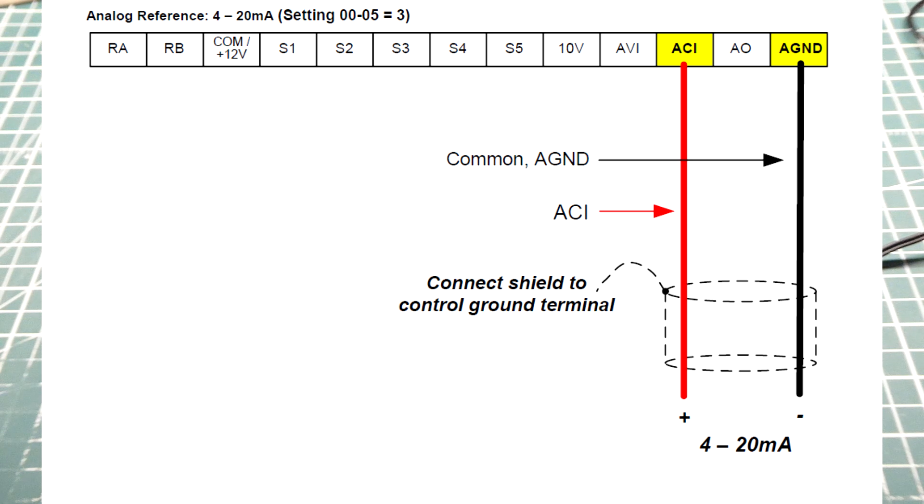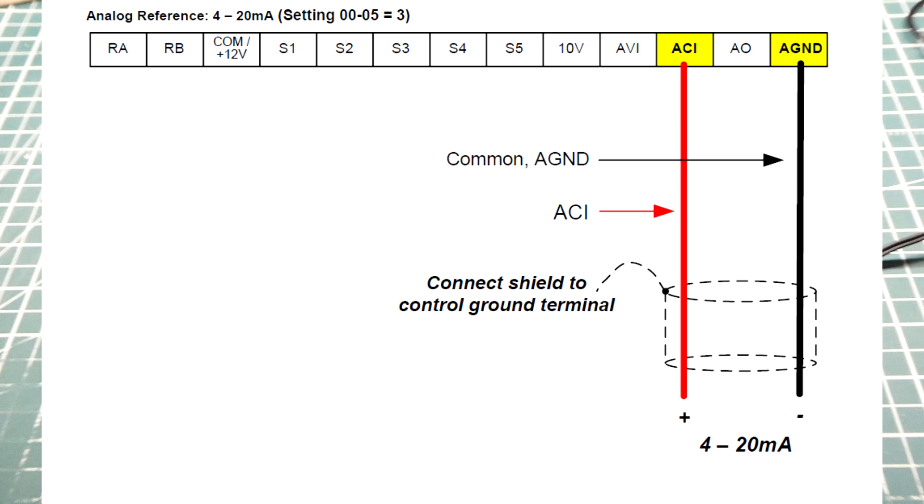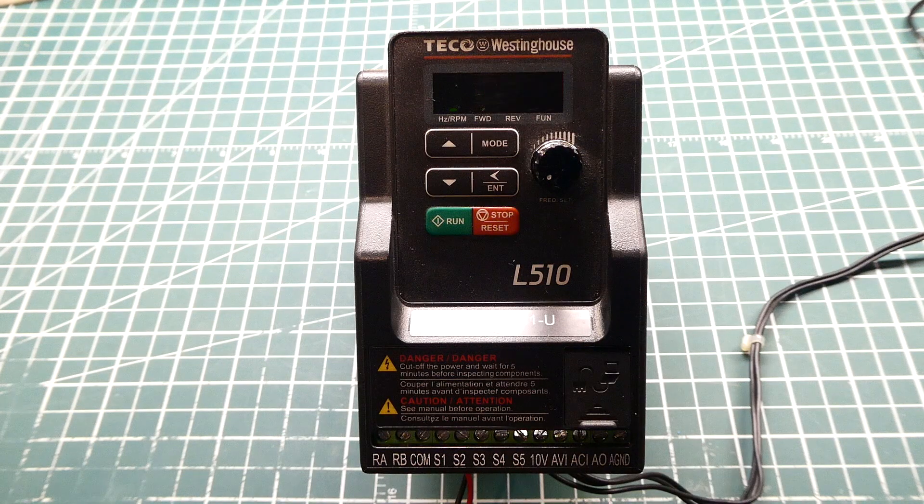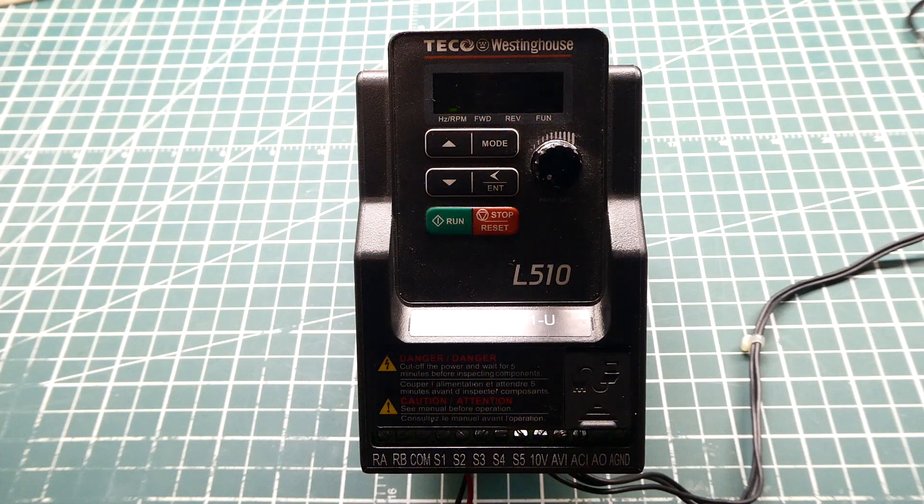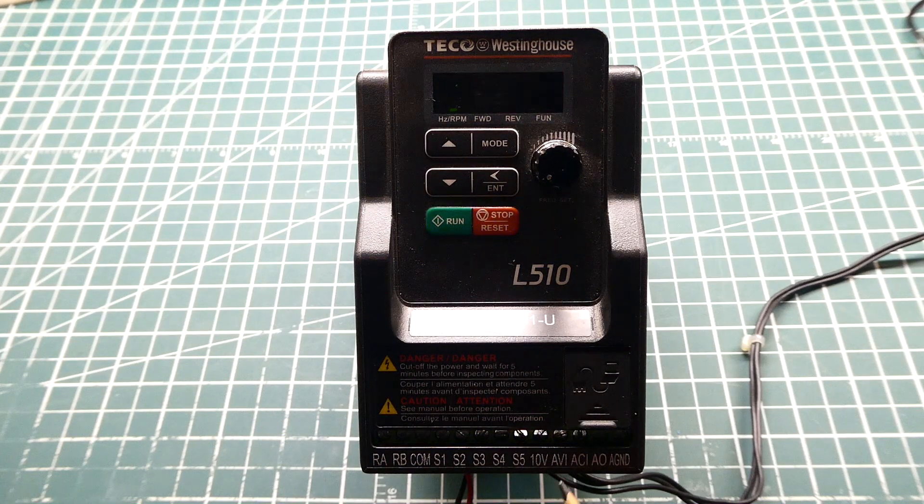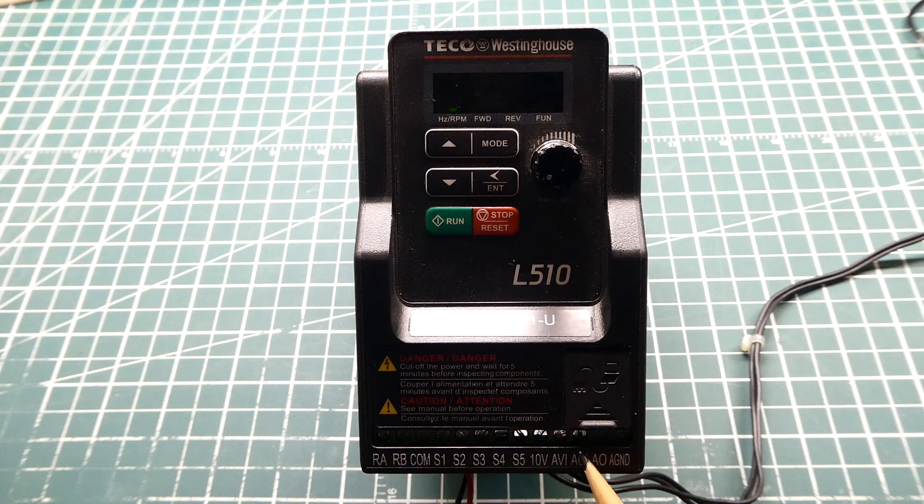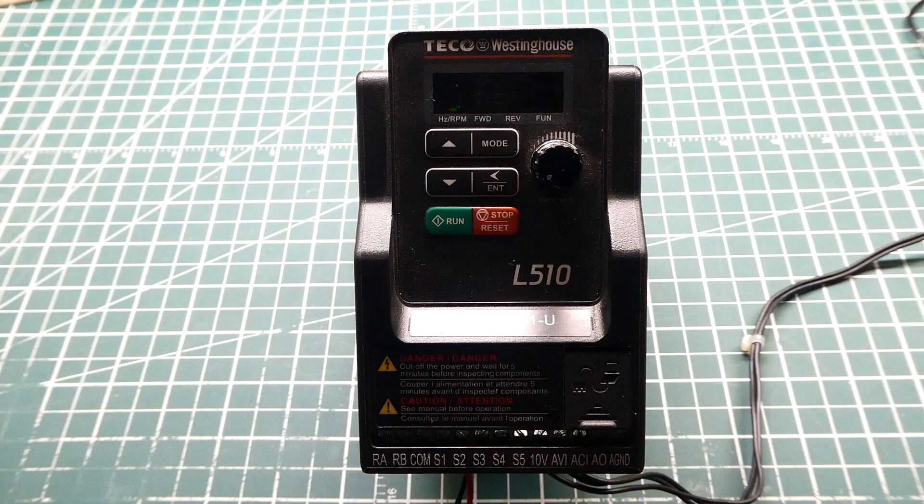The second way we can control the speed and direction of a motor is using the ACI input, that's the current input, that's a 4 to 20 milliamp current loop.